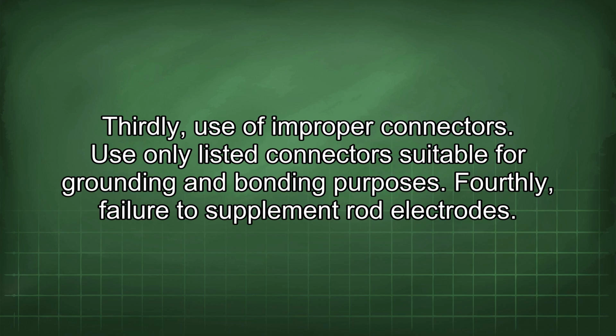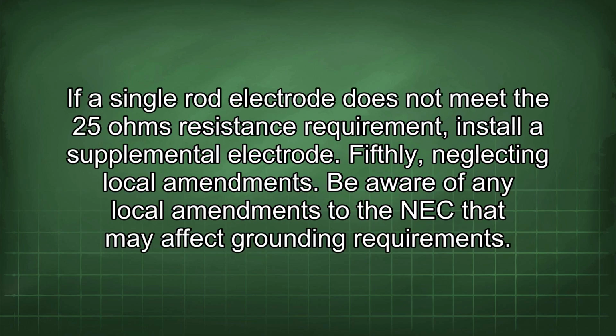Fourthly, failure to supplement rod electrodes. If a single rod electrode does not meet the 25 ohms resistance requirement, install a supplemental electrode. Fifthly, neglecting local amendments. Be aware of any local amendments to the NEC that may affect grounding requirements.